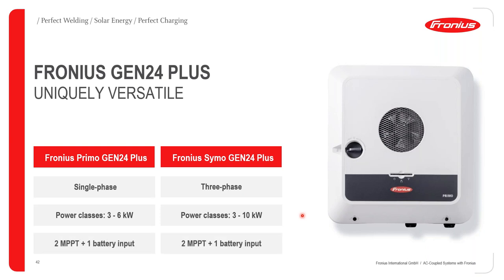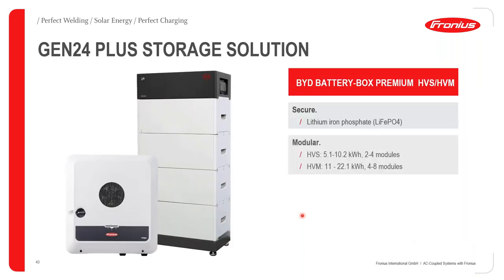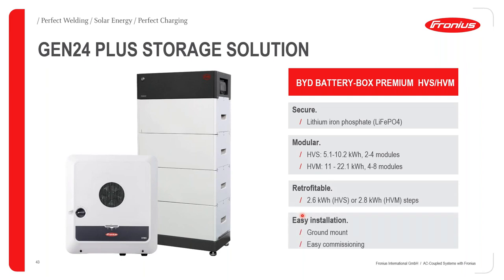With both of these inverters, we have two MPPT trackers integrated, and we also have one battery input, which is a high voltage battery input. Please do take note that this GEN24 system will only be compatible with BYD Battery-Box Premium HVS and HVM batteries, which is basically a high voltage lithium iron phosphate technology. It comes in a very modular structure. So we have two variants, the HVS and HVM.